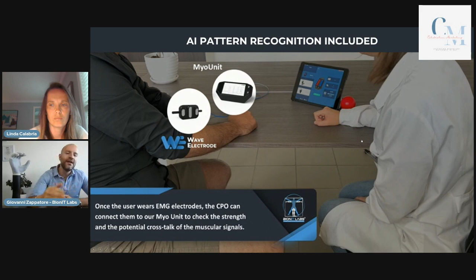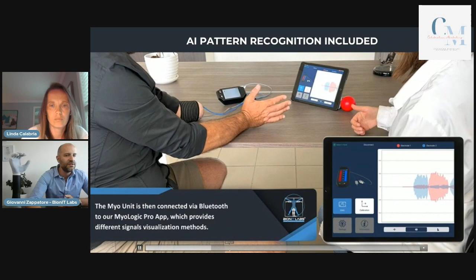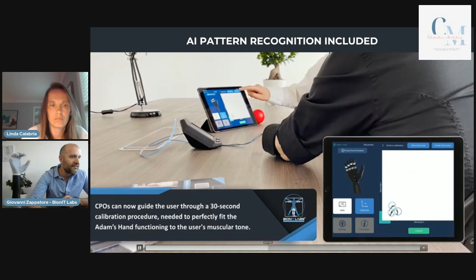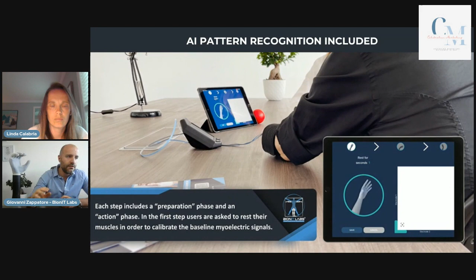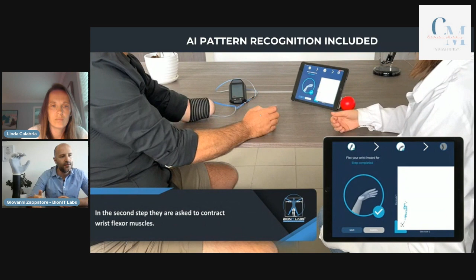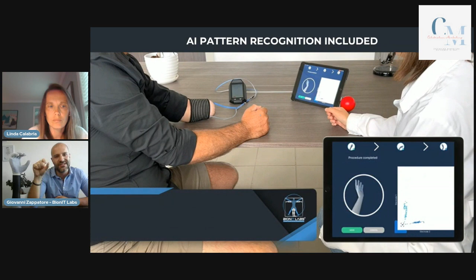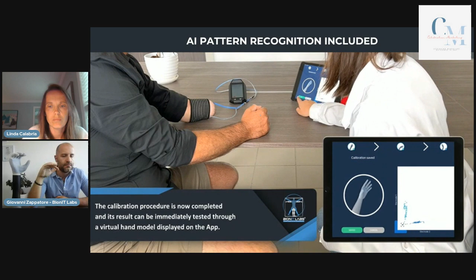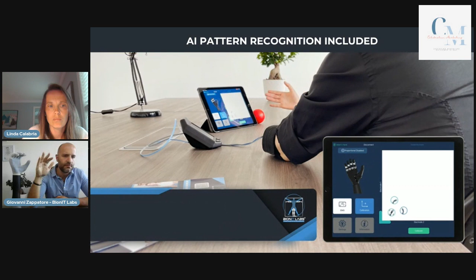artificial intelligence. Let's say it's a pattern recognition algorithm that allows the device to perfectly fit each single patient's muscle tone. So here you can see you have at first the standard procedure through which you're looking for the best myoelectric site to control the device. But after that, we get a calibration procedure. So the patient can run through a 15 second calibration. During the first step, he has to rest for 3 seconds. Then to close the hand, so contract wrist flexors and hold close for 5 seconds. And at the end, on the opposite, to open the hand, so contract wrist extensors for 5 seconds. So basically what we do is we get the signals of both the electrodes at the same time. Once done, you just have to save, and it's done. The patient can already control the device without setting any threshold, any delay, nothing.